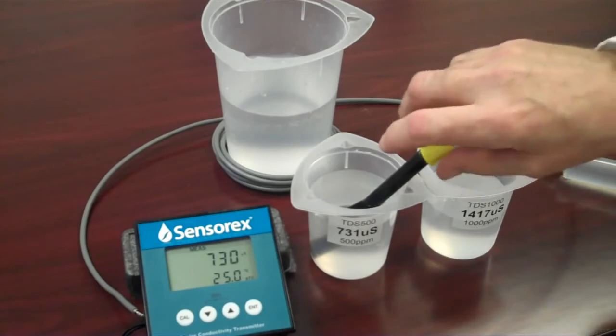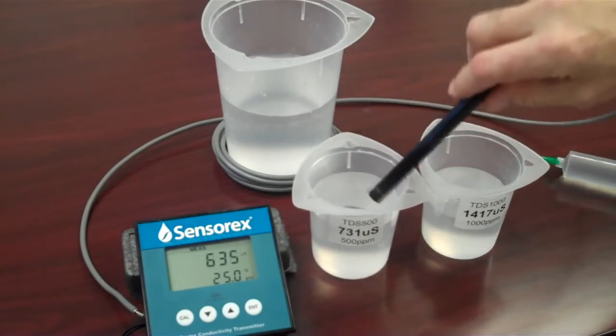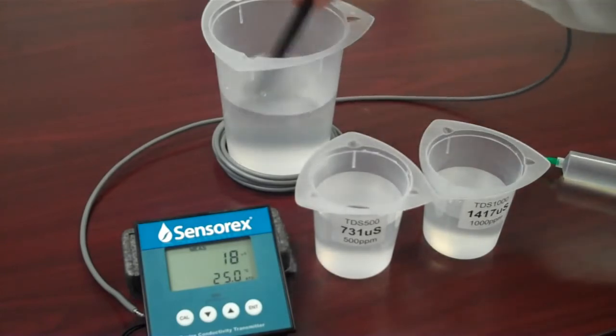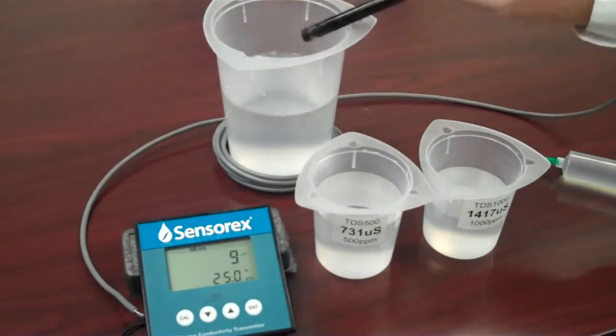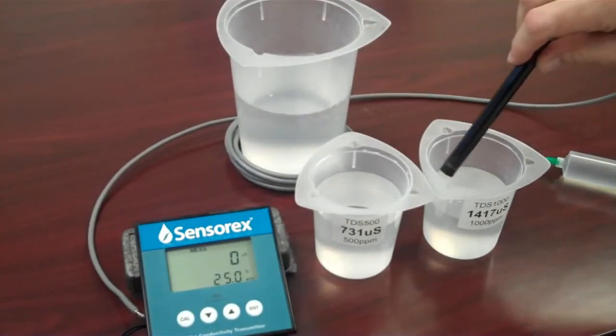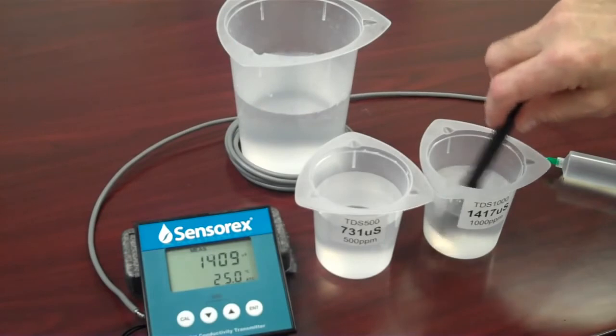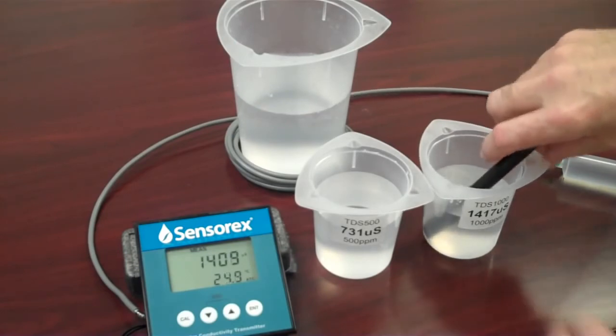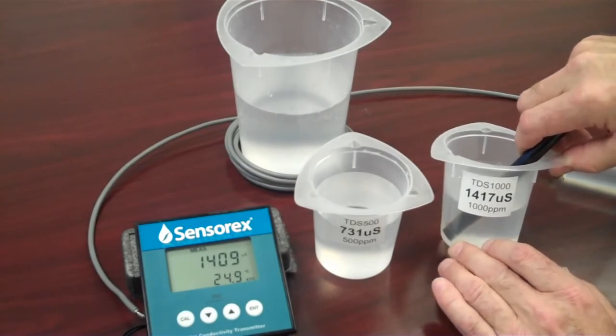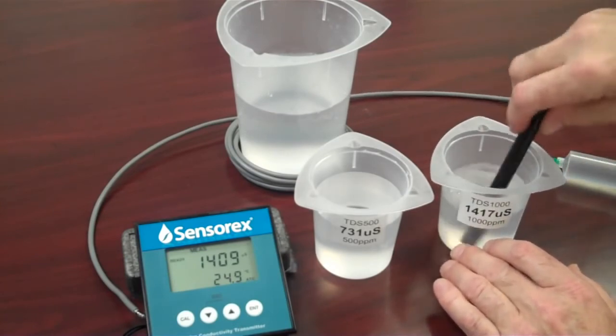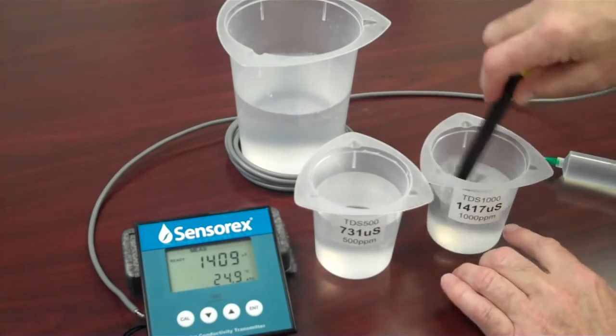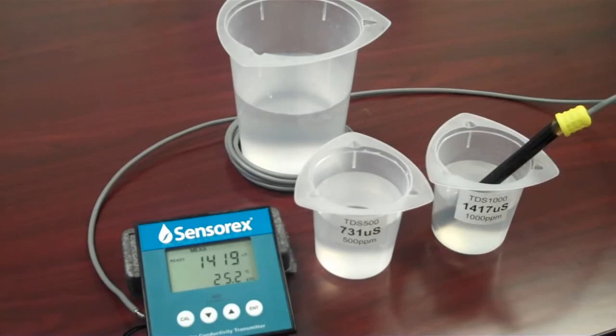In today's example, I've selected a second standard that has a conductivity of about twice my calibration standard. I'll be going from 731 microsiemens into a standard that has a conductivity of 1,417 microsiemens. The 1417 microsiemen solution has a total dissolved solids of 1,000 parts per million. Again, stirring the solution to provide stable readings. Okay, my meter has stabilized. I'm reading 1,419 microsiemens. The standard that it's in is reading 1417, so it has very excellent agreement.